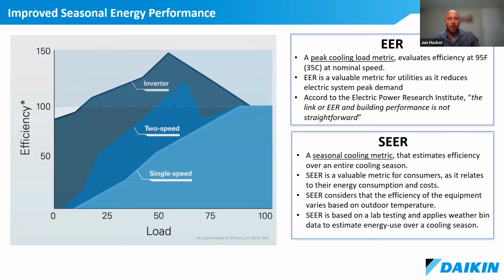So, I was talking about it in the last slide a little bit, but inverter efficiency improves at lower loads, and the efficiency actually exceeds its full load efficiency, or 100% load efficiency. So you can see here, single speed equipment efficiency kind of peaks at full load and gradually falls off. I don't entirely agree with the graphic here that the efficiency goes to zero, but I do agree with the overall trend that it does fall as load is reduced because the equipment will short cycle. But for inverter equipment, the efficiency increases as load reduces.